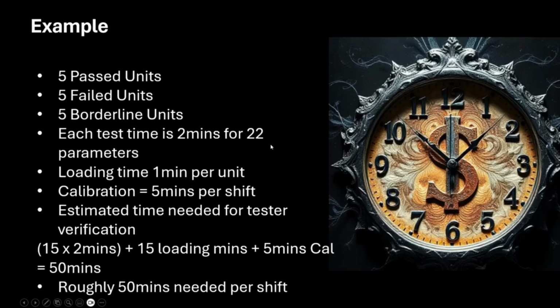So for example, in the ideal world, I choose 5 pass units, 5 fail units, 5 borderline units. And let's say each test time is about 2 minutes for 22 parameters, and loading time, where I change from one unit to another, takes about a minute. It's a bit slow, but just for example. Then calibration, let's say before we test, takes about 5 minutes per shift. So the estimated time for tester verification is roughly about 50 minutes.